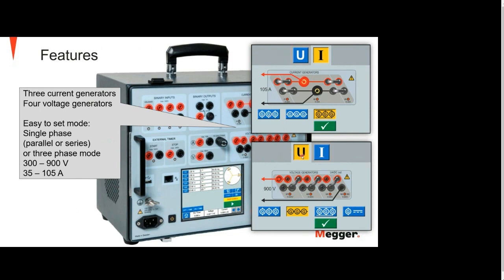And here we have the voltage channel. In this case, it's in series mode. Then you can deliver 900 volts from the generators. But we can also be in parallel mode, in individual mode, three-phase mode. If you are in individual mode with the current generators, we can run up to 35 amps on each generator. And in voltage individual mode, we can run up to 300 volts on each generator.